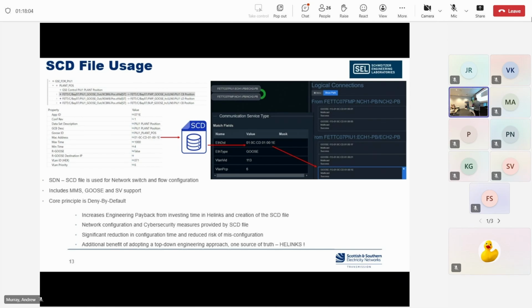We've seen a lot of benefit from that. If we have a network of around 10 switches, we can reconfigure the whole network in about half an hour to 40 minutes by using the SCD file to configure all the parameters. One source of truth is Helinks - it means our libraries, our network configurations, and all our Goose messaging are all in Helinks. It was really good to have that as an overall independent tool.